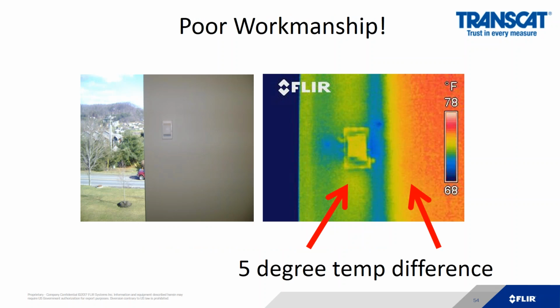This is another classic picture. Companies may overrun their heating and air conditioning because the thermostat was put in the wrong position. So this thermostat has been put in an uninsulated portion of the wall. The right side is red where there's insulation. The left side of the stud and the nail pop that you can see there, that's where it's exposed outdoors. So the customer is not getting the right internal temperature to set his HVAC equipment. This happens all the time.